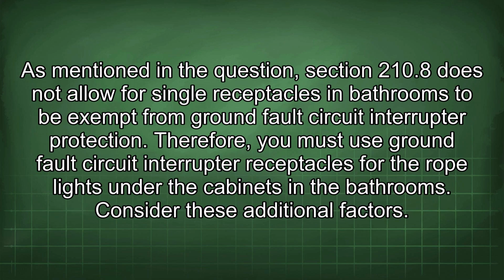As mentioned in the question, Section 210.8 does not allow for single receptacles in bathrooms to be exempt from ground fault circuit interrupter protection. Therefore, you must use ground fault circuit interrupter receptacles for the rope lights under the cabinets in the bathrooms. Consider these additional factors.